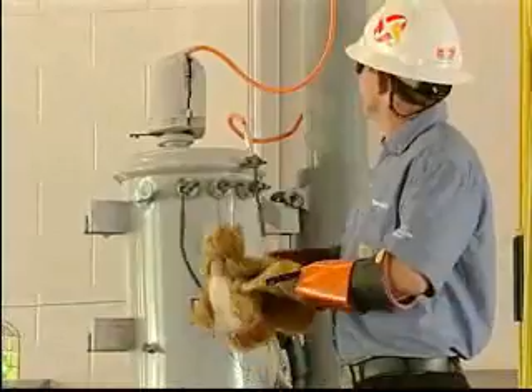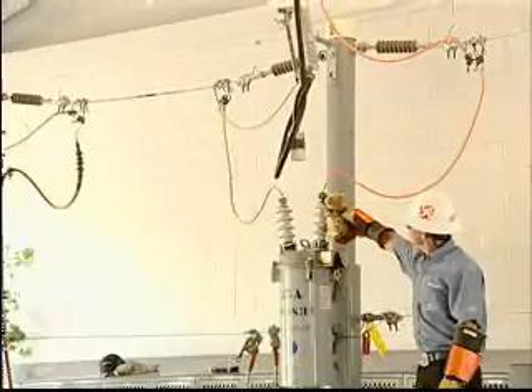An animal sitting on top of that transformer tank—that tank has a connection point wired right to that neutral, and the neutral's attached to ground rods on good old Mother Earth. So he's sitting on a dead ground, a dead short. When he leans over and makes contact with the mechanical connection on top of the porcelain bushing, that's a dead short. That's going to cause a flash and burn something up—burn a wire down, blow a fuse, something like that.